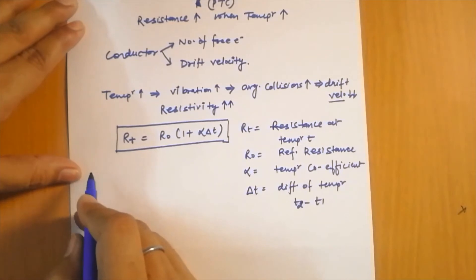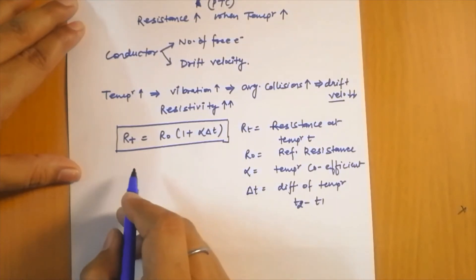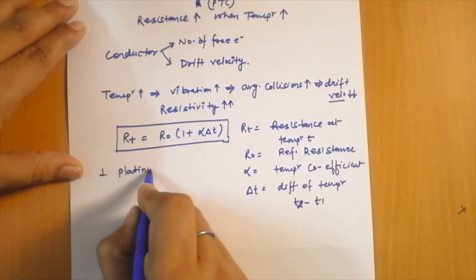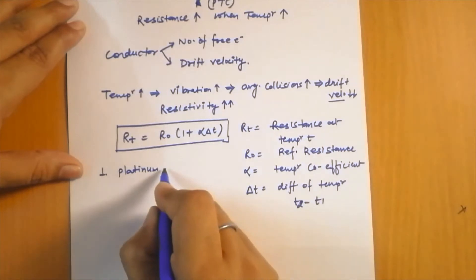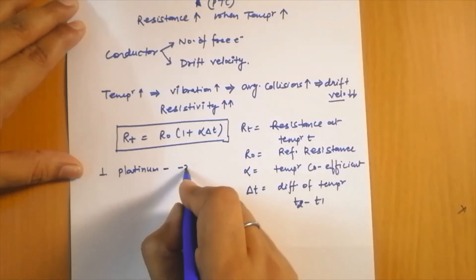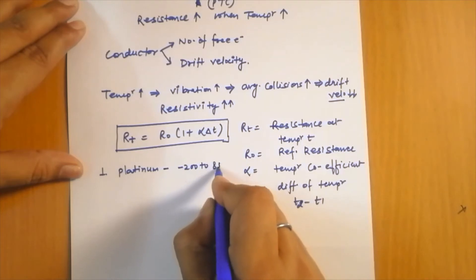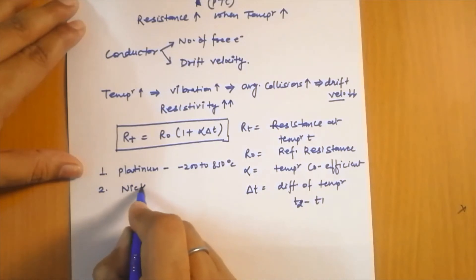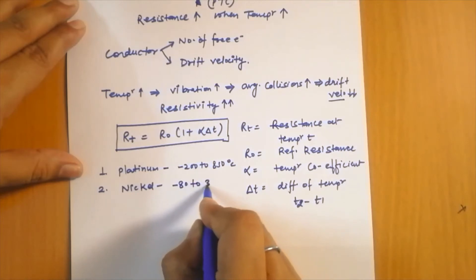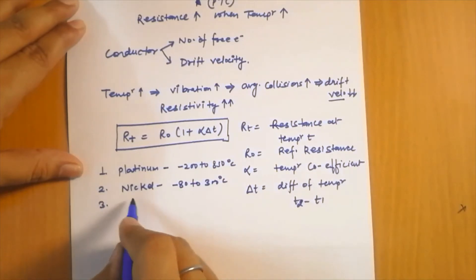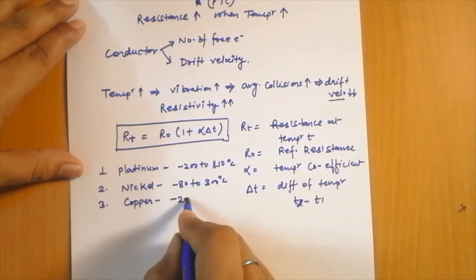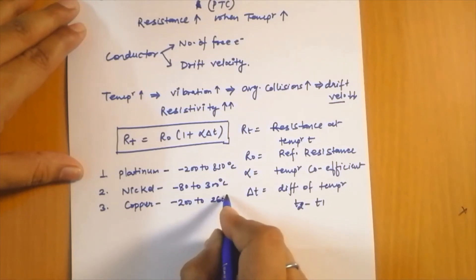The materials used in the construction of RTDs are: platinum, used in the temperature range of minus 200 to 850 degrees centigrade; nickel, used for a temperature range from minus 80 to 300 degrees centigrade; and copper, used for a temperature range of minus 200 to 260 degrees centigrade.